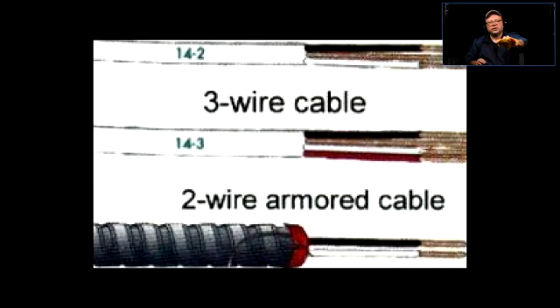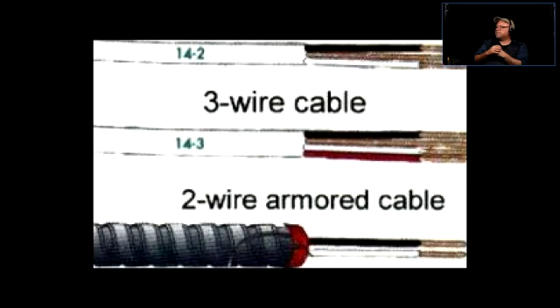By current carrying conductor: a current carrying conductor under normal conditions is supposed to carry electric current. Electricity is going to flow through those wires. Those wires are used to complete an electrical circuit and provide service to some device, whether it's a light bulb, a toaster, a hair dryer, or whatnot. The bonding wire, under normal circumstances, is not supposed to carry current. It's supposed to serve as a safety feature. If something goes wrong, that wire is supposed to take the hit instead of you, for example if you touch something in the wrong way.